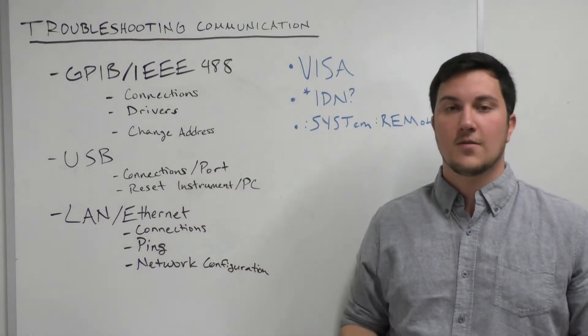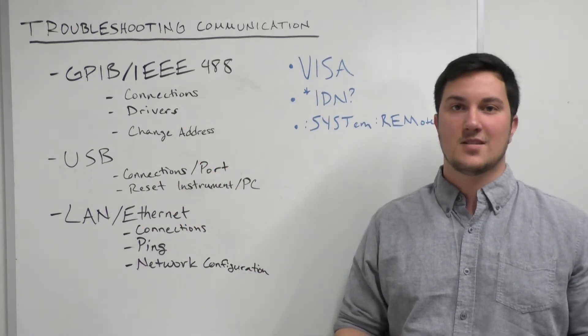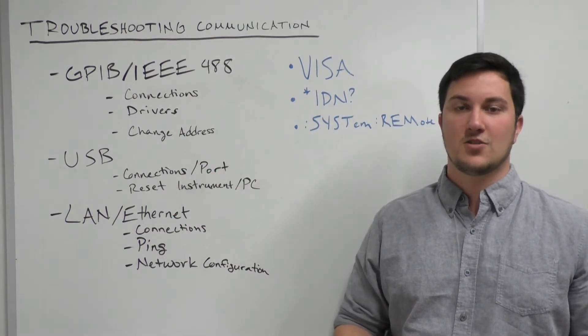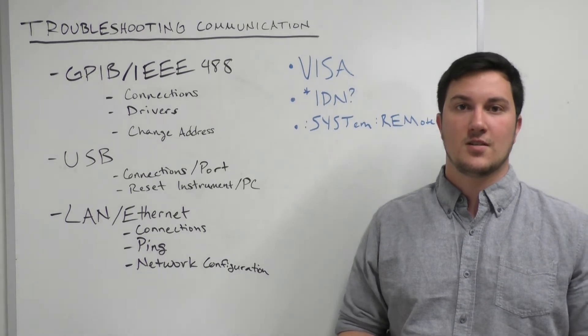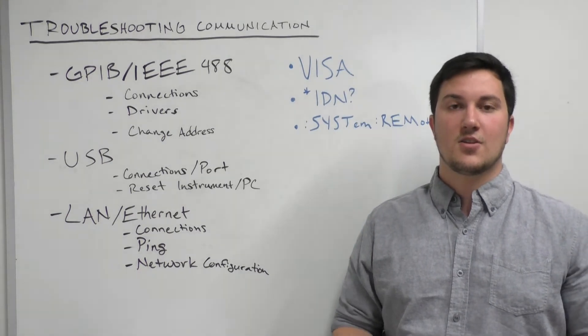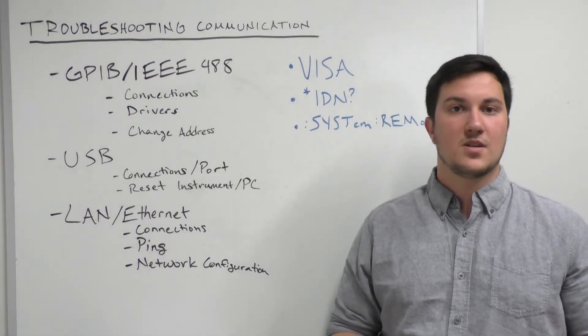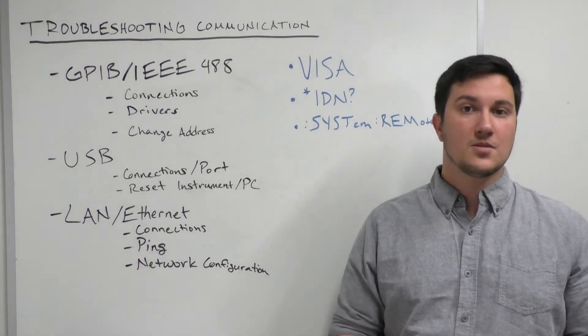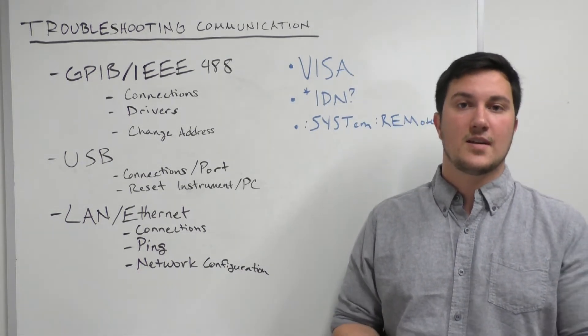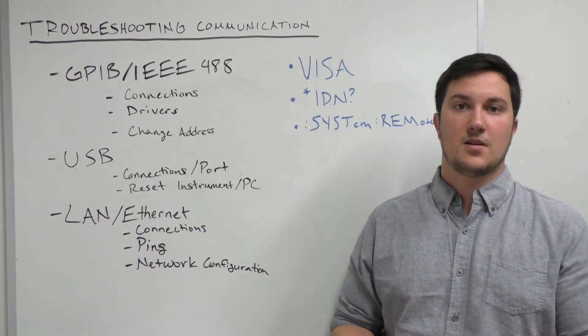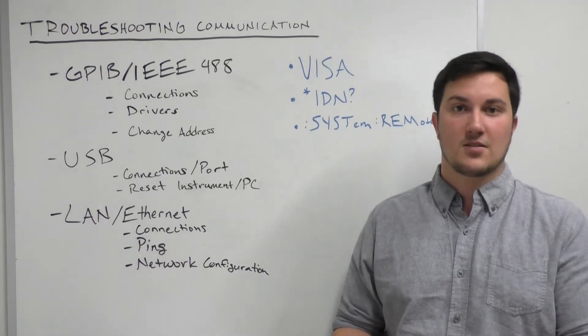The first step to troubleshooting any of these interfaces would be ensuring a good connection. That means securely connecting any USB or LAN cables and screwing down any GPIB adapters or connectors.